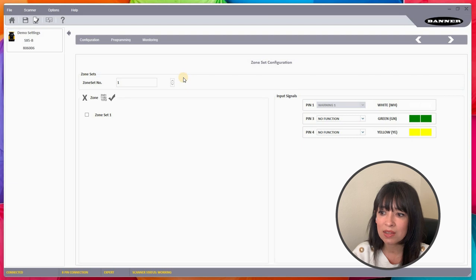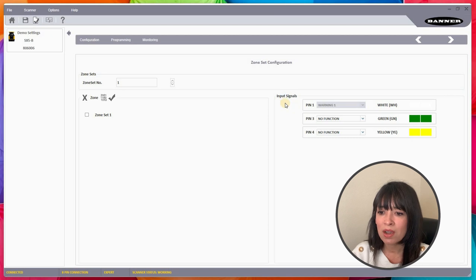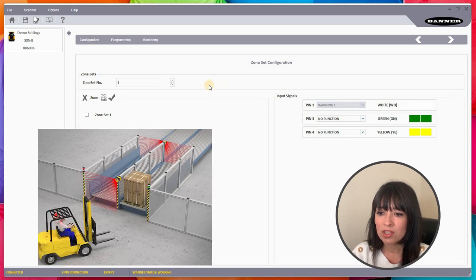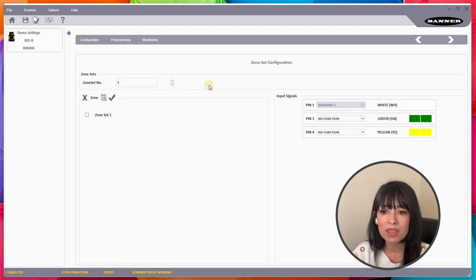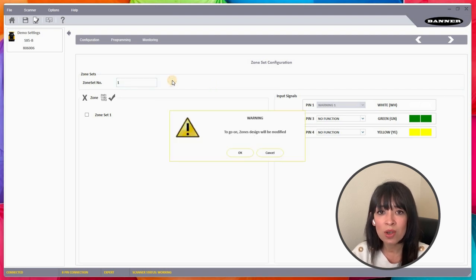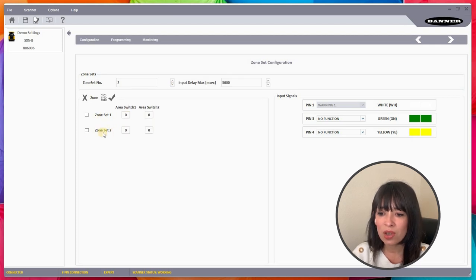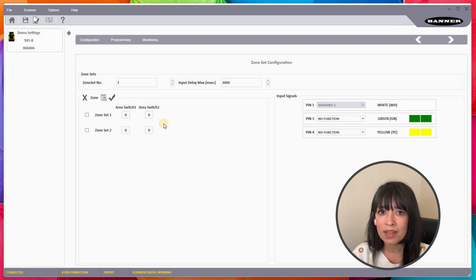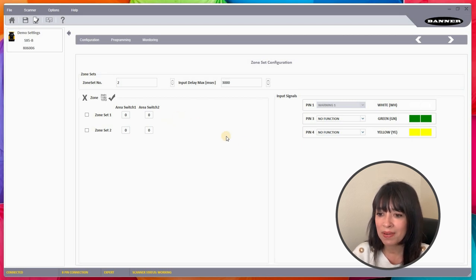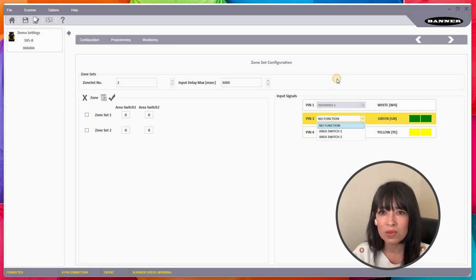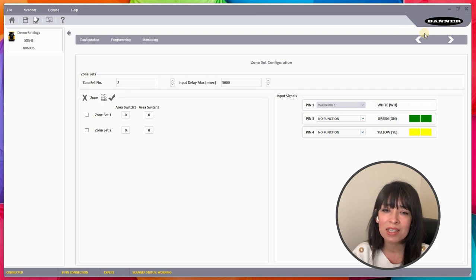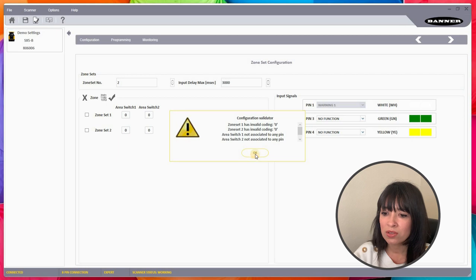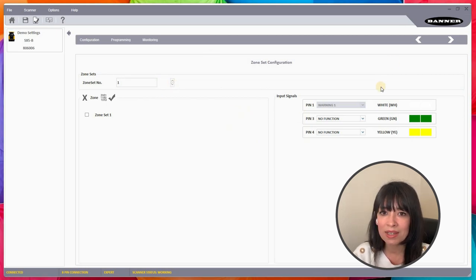I'll go ahead and click the next button. Zone sets. A lot of people have questions on what exactly are zone sets in this part of the software. Here's a few pictures that I'm going to post up about different applications that require different zone set configurations. For example, if you had an application with an AGV, you would use inputs on the safety scanner to tell it to run different zones at specific times. I can set each zone as these sensors turn on. It will tell me to do zone set one, zone set two, etc. On this particular device I only have two zone sets available, but in our higher end products you can do up to 70 zone sets. That's pretty neat. This is where you can do it. You would tie those sensors in to tell the scanner which zone set to execute.